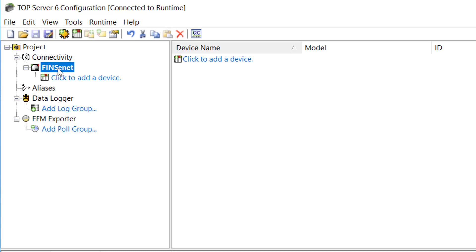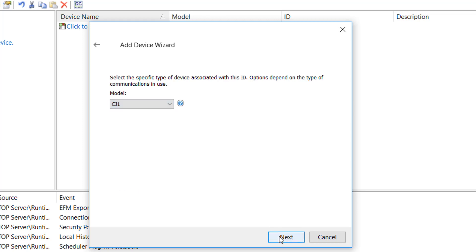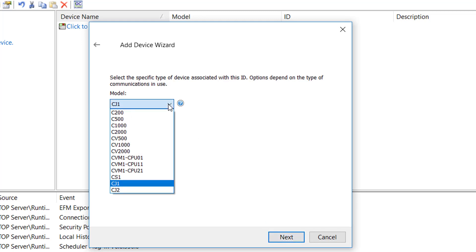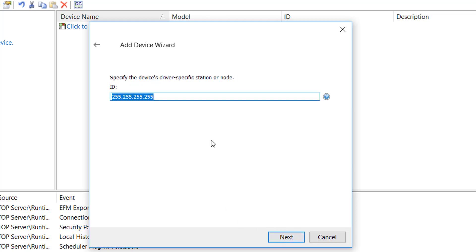Now I'm going to configure a device by clicking Add Device. I'm going to define it as Omron CJ1 because I'm connecting to an Omron CJ1 PLC, then click Next. I need to select the device model — in TopServer, where you have multiple models available, this defines the available addressing supported for that particular controller. I'll select CJ1 from the model list, which corresponds to my actual Omron controller, and click Next. Here is where we actually define the IP address assigned to the Omron PLC — I'll type in 192.168.111.4 and click Next. Remember that 4, as we'll see it come up again when we get to our FINS parameters.